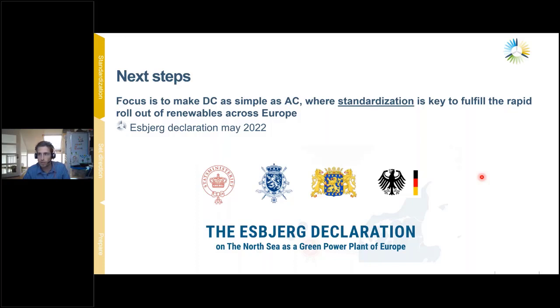So then about standardization, what do I mean with this? It is to create together a common technical language for high voltage multi-terminal DC. All components in the system need to work in harmony as a single family: cables, converters, fault separation devices like breakers. There should also be a master controller to provide set points across the whole network. This is very important to make such a next step.